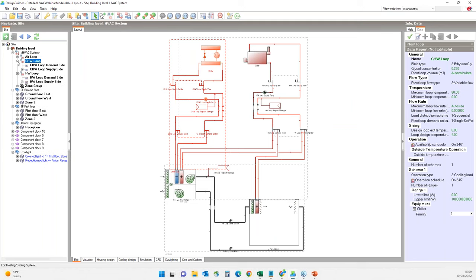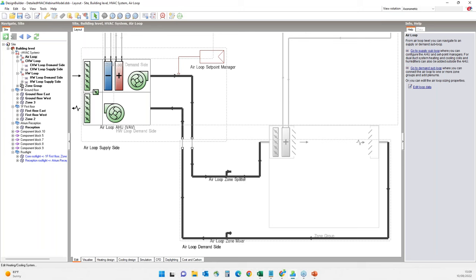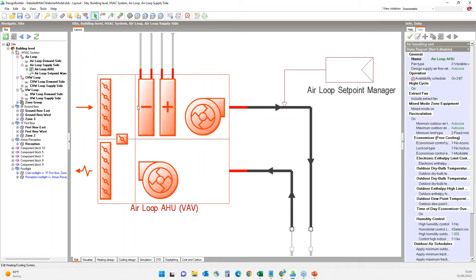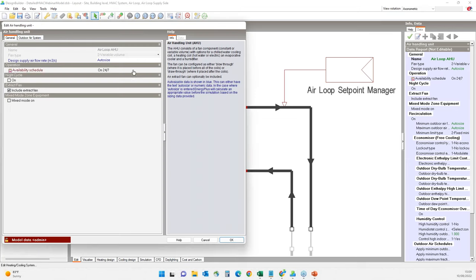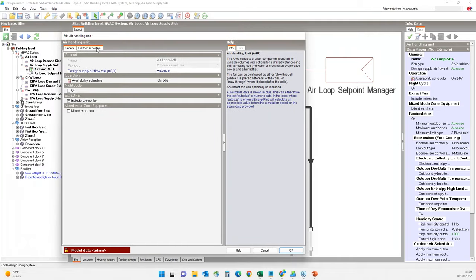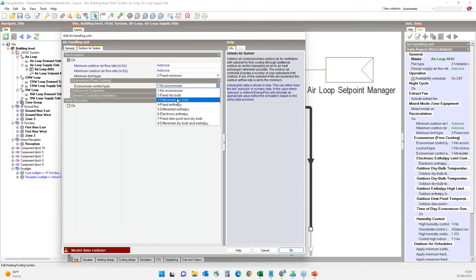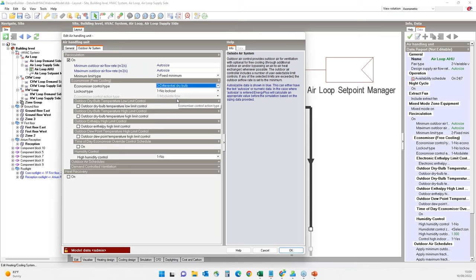Like the hot water loop, we have the chilled water loop as well, which also includes supply and demand side sub-loops. The air loop has the air handling unit — currently a variable air volume system. On the air handling unit's edit dialog we can change the outdoor air system settings. On the outdoor air system tab there is an option for adding an economizer, such as fixed dry-bulb, differential dry-bulb, or enthalpy-based. Economizers are controllers which can provide enhanced fresh air directly from outside if that air is cool enough, providing free cooling.